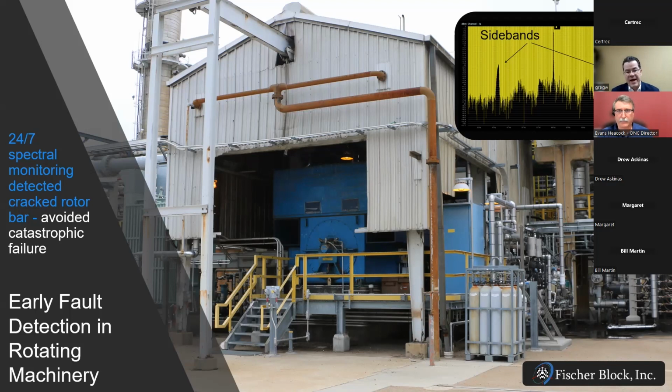What's interesting is the faster you sample, obviously it's intuitive that you can see higher frequency components. But interestingly, the longer you sample before you do your FFT, the longer that data set in time means the higher the resolution you get on the chart. And so it's a combination of sample rate and duration of sampling. And those two kind of work against each other, because the higher the sample rate and the longer you sample, the data set becomes bigger, and then you need more storage and bigger bandwidth. So it's a trade-off, and so we actually adjust our sample rate and our duration of samples based on the application, and we'll do multiple versions of each on a given asset.